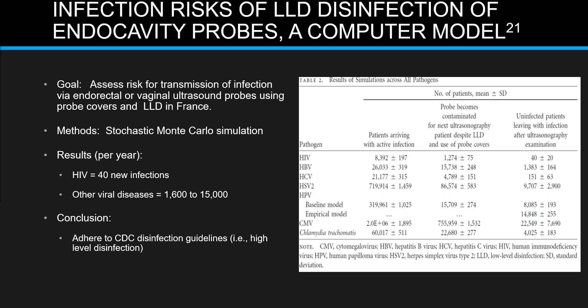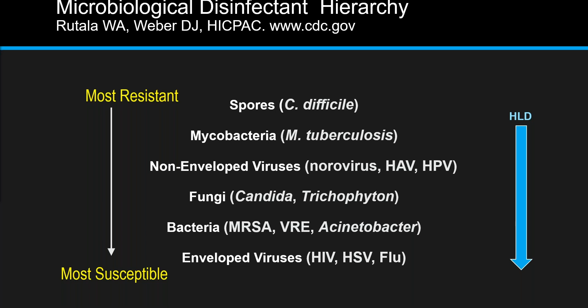So as we talk about the differences between what high-level disinfection accomplishes, this little schematic demonstrates that. So for sterilization, that is defined as the complete elimination of all possible microbes. High-level disinfection will eliminate all microbes except for high numbers of spores. It will eliminate low numbers, but not high numbers. But it will kill off all the mycobacteria, all the viruses, enveloped and non-enveloped, particularly important for rectal and vaginal probes as HPV. It will eliminate all the fungi and all the bacteria.